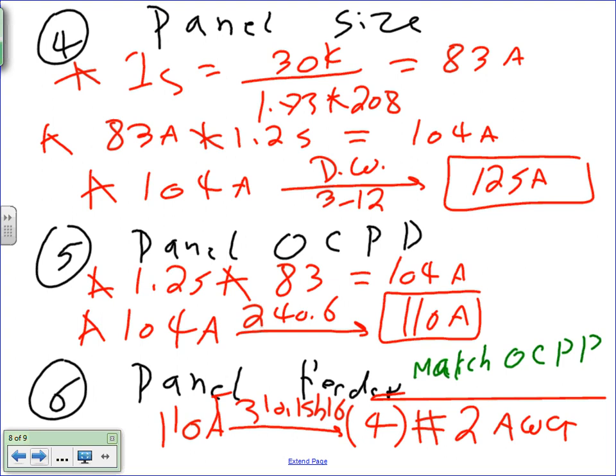Number 2. Now, I can't emphasize this enough: you go to a company and say my panel has a bus of 125, I don't want to limit that bus to only 110. It might actually be a stupid idea. So I need to put an overcurrent protection device 125 in it to match the buses. Great. Then what you need to do is upsize your conductors, and you're okay with that. No problem with that.